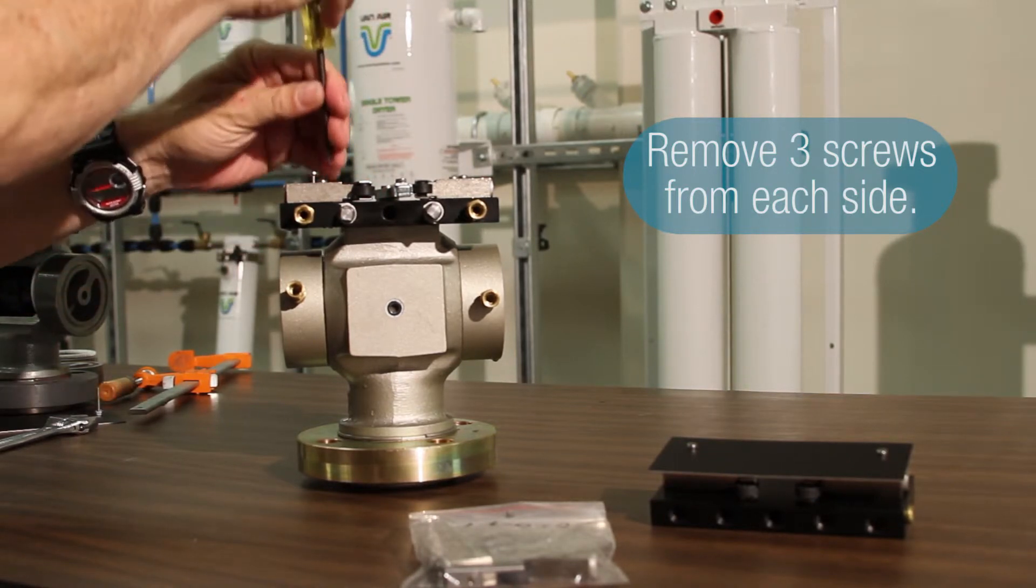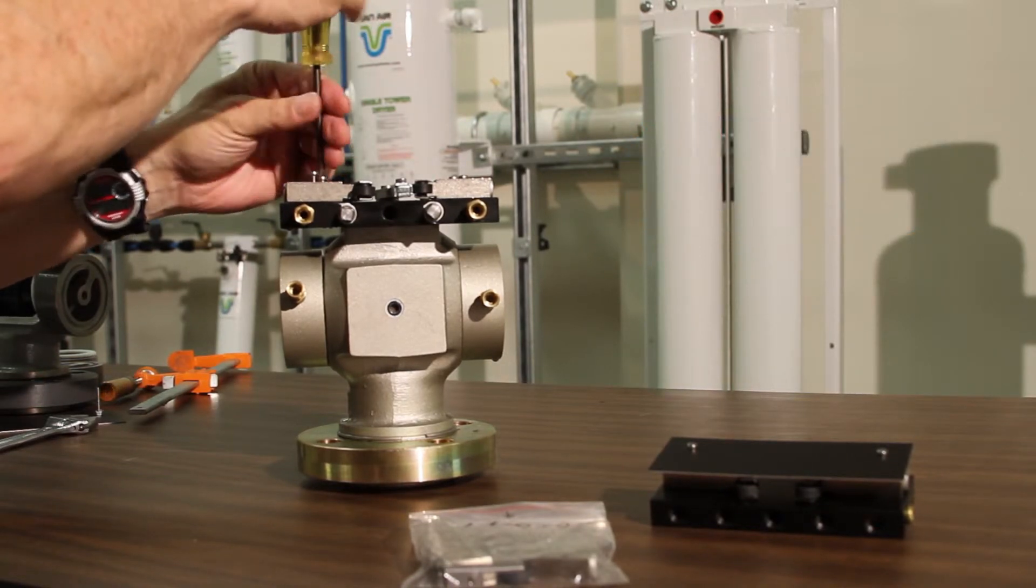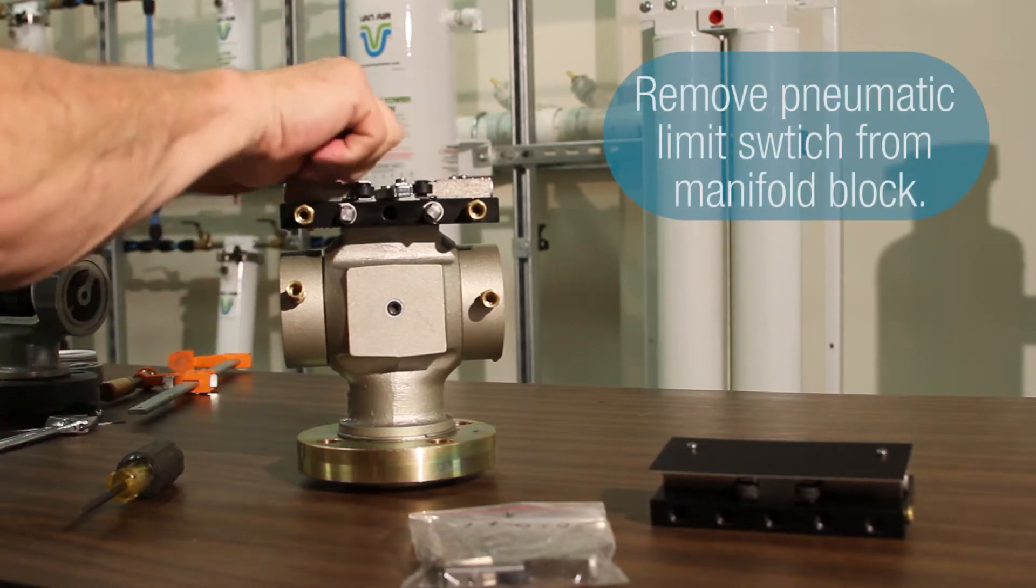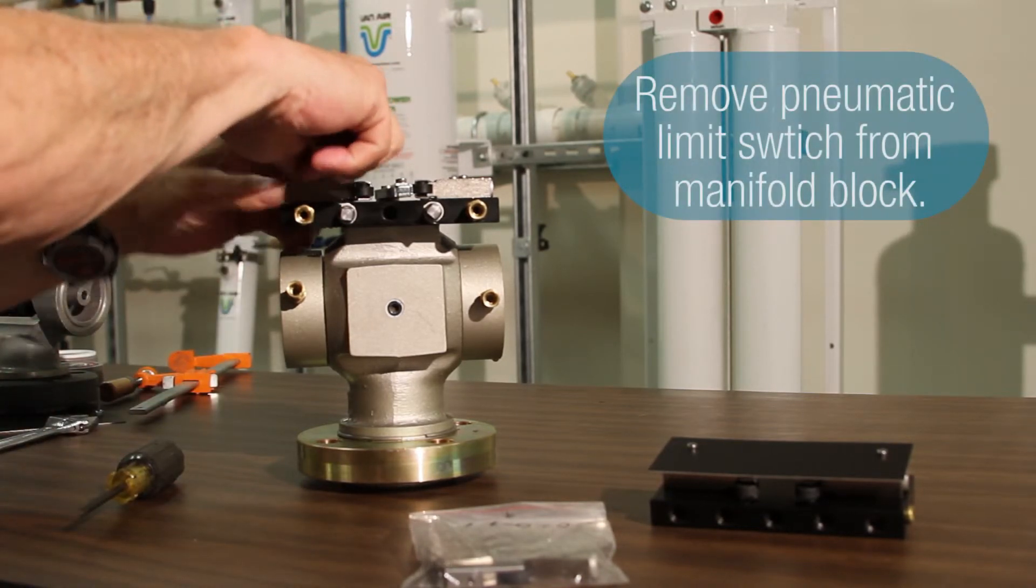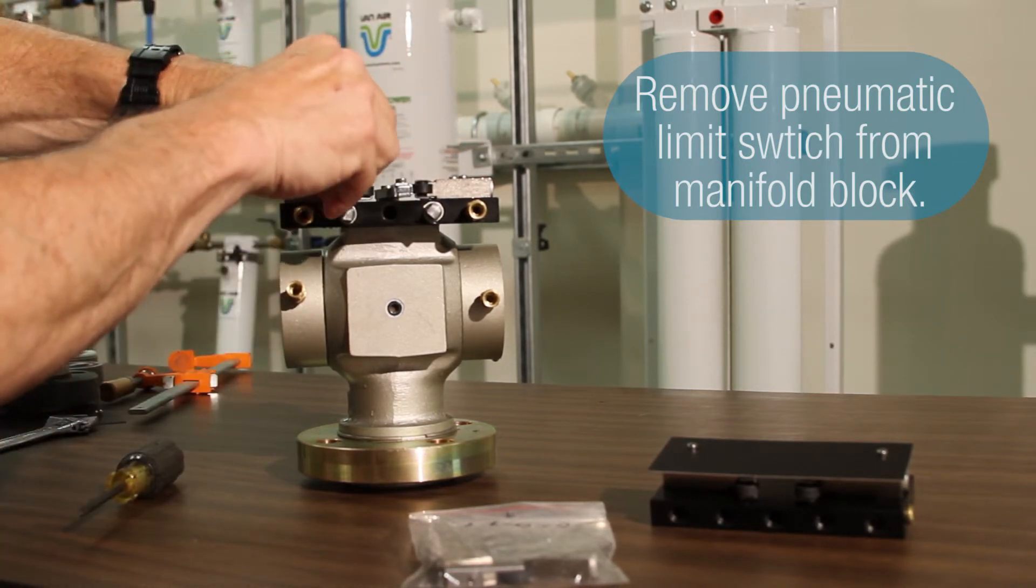Now, the other thing is to take the valve apart to pull the shuttle out of the valve. You actually literally have to take one of the pneumatic limit switches off the manifold block to allow the position indicator arm to move far enough to allow the shuttle to come out of the valve body.